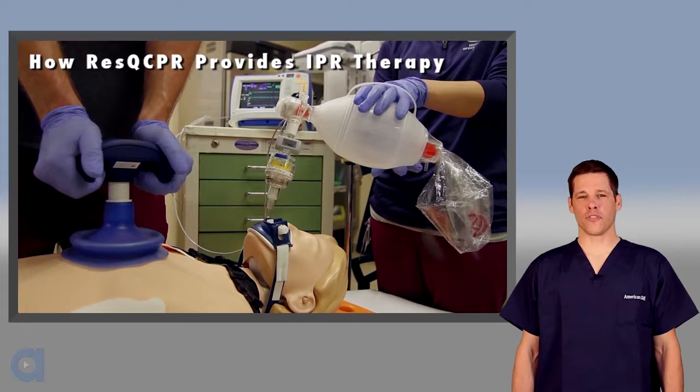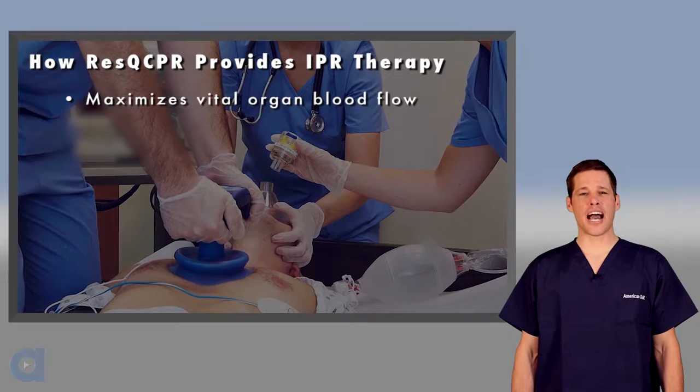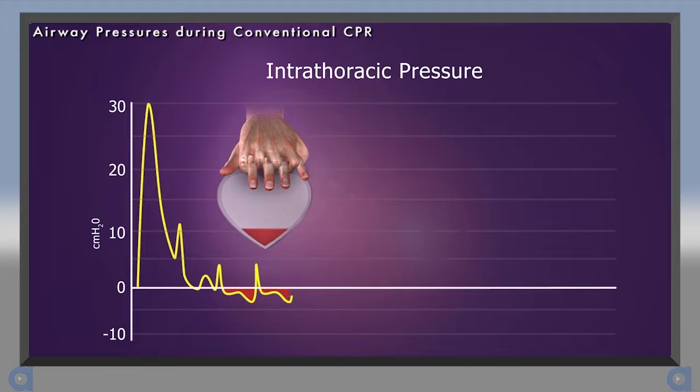Now that you understand how the ResQPOD and ResQPUMP each work, let's talk about the benefits of using them together to perform ResQCPR, which is the performance of ACD-CPR in conjunction with an ITD. This device combination provides IPR therapy to maximize vital organ blood flow and provide perfusion on demand during cardiac arrest. In the United States, the ResQCPR system is the only CPR device combination with an FDA-approved indication for improving the likelihood of survival in adult patients in non-traumatic cardiac arrest. The ResQPUMP is the only FDA-approved device that allows the performance of ACD-CPR with up to 10 kilograms of active decompression. There are no contraindications to its use, but please refer to the product instructions for use for a complete listing of all warnings and precautions.